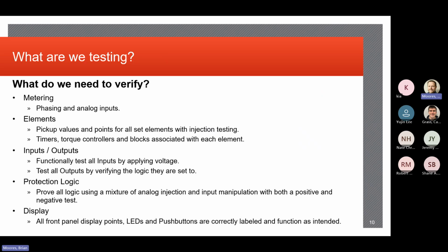We have a 2000 to 5 CT ratio that's connected to the relay, and we put 5 amps into the relay. What would the relay think it's seeing from a primary perspective? 2000. There you go. Right. So we verify that. If we're expecting 2000 to 5, the drawings say 2000 to 5, and we put 5 amps in and we see 3000 amps, we have a problem. Right. So that's the kind of stuff we're looking at.